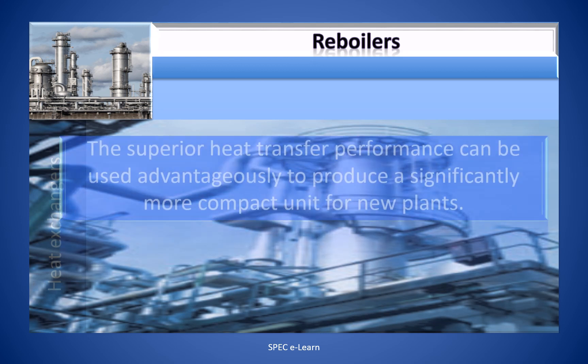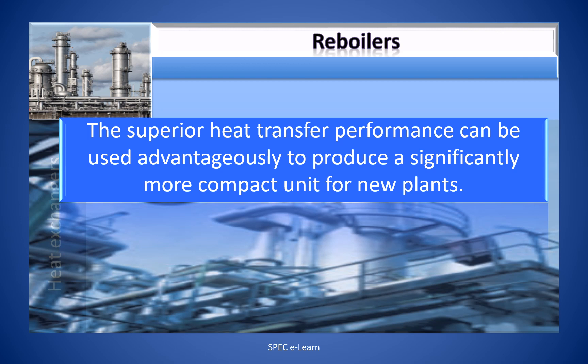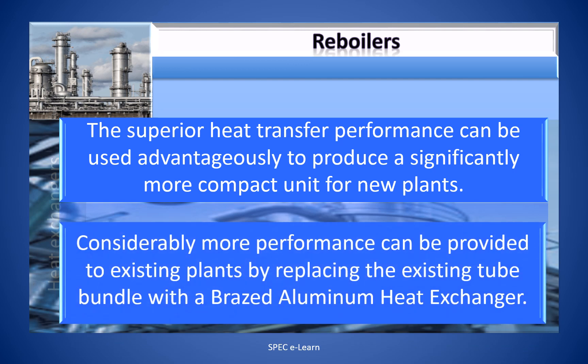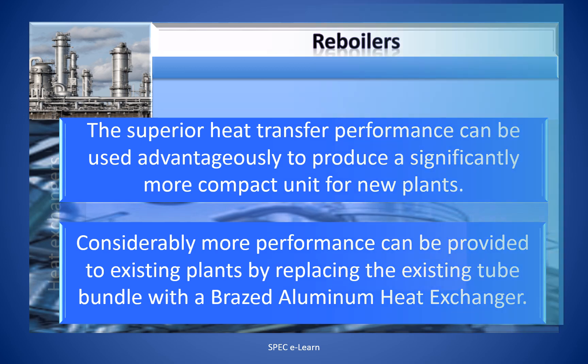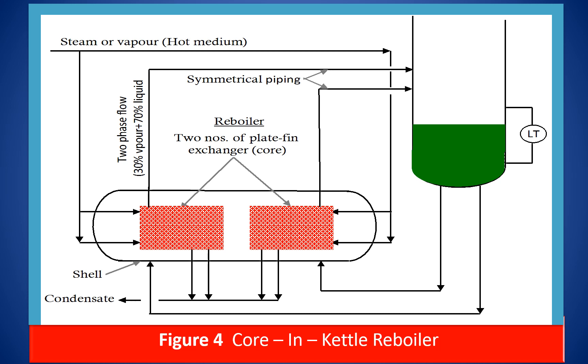The superior heat transfer performance can be used advantageously to produce a significantly more compact unit for new plants. Considerably more performance can be provided to existing plants by replacing the existing tube bundle with a brazed aluminum heat exchanger. The warm stream fluid, which is usually steam, enters the brazed aluminum heat exchanger through steel nozzles on the vessel shell. The inlet nozzles of the heat exchanger are connected to the inlet pipes coming from the column bottom by aluminum to stainless steel transition couplings.